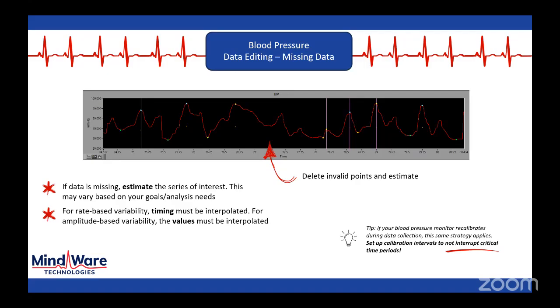Another point to make here is that sometimes your signal can be disrupted due to the instrument that you're using. So these continuous blood pressure systems use the arm cuff and the measurement at the extremities because the arm cuff provides this baseline level assessment of blood pressure, and then the continual cuffs kind of keep that going for a while. But over time, those do get out of calibration. They get out of range. And so you'll see signal degrade. You'll see values change in ways that are less likely to be physiologically plausible. And so what those instruments will typically do is they will recalibrate at some point. They will take another measurement from the arm to get things back on track so that you know that you're in the range that a person actually is.